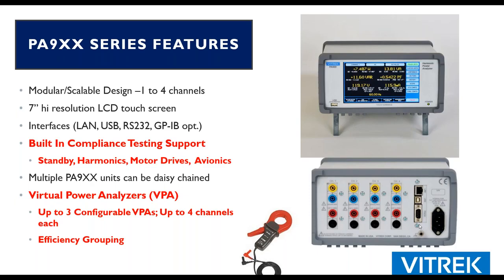The PA900 series power analyzers can also be daisy chained. You probably won't need that many, but as you can see on the back panel, we have 4 slots for 4 different channels of voltage and current inputs. You can daisy chain multiple units to get 8, 12, or 16 channels of power analysis capability, all tied in to be synchronously measured. So if you have something on channel 12 you want to compare to channel 1, you can easily do that.